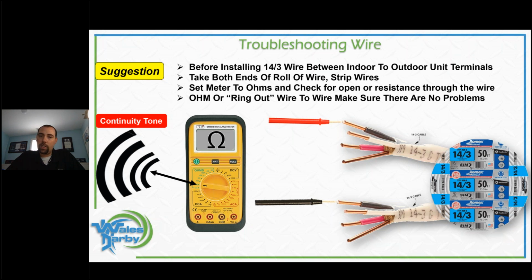He ran into a situation where he did an installation, and unfortunately, after it was all done, he thought he was good, ready to go home. He fires this thing up and he's got a communication error. Drove him nuts, checked his wires, everything was clean, pulled the wires off, went and did a continuity check, black to black, red to red, white to white, ground to ground.